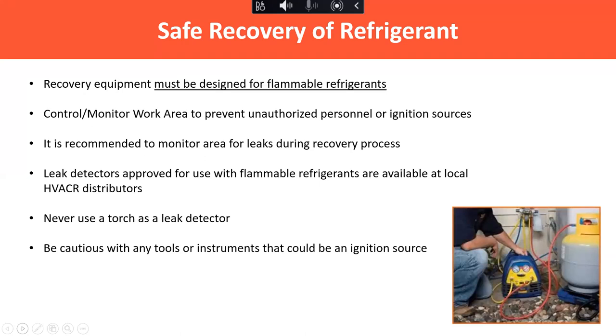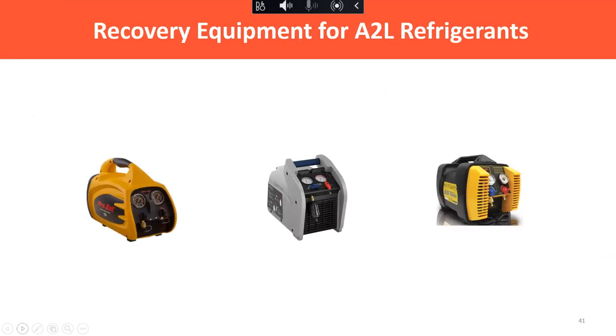This is the one piece of equipment where you're going to have to check, and you may need to get new equipment based on how those were designed. They are available out there. I think on the next chart we have some pictures of them, but a number of leading vendors, the usual suspects who sell this equipment, if you ask and check, have A2L rated recovery equipment out there. So the next chart is just a picture of some of those. We can go on, skip on to the next one, please.